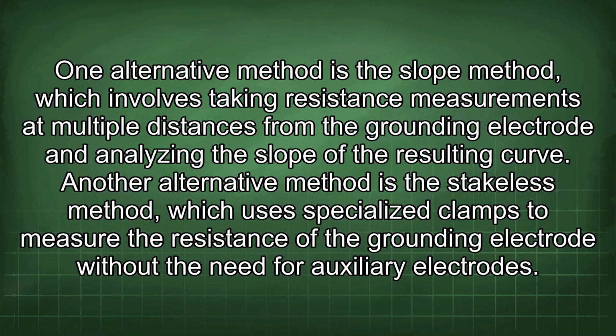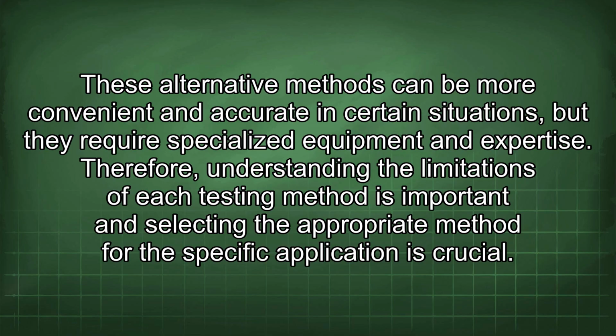Another alternative method is the stakeless method, which uses specialized clamps to measure the resistance of the grounding electrode without the need for auxiliary electrodes. These alternative methods can be more convenient and accurate in certain situations, but they require specialized equipment and expertise.